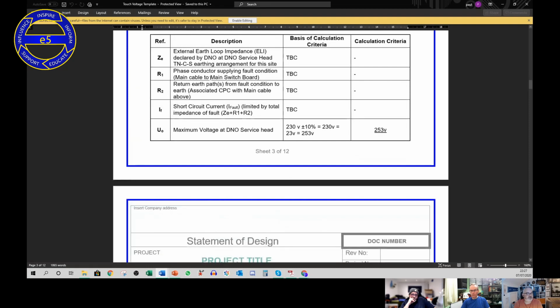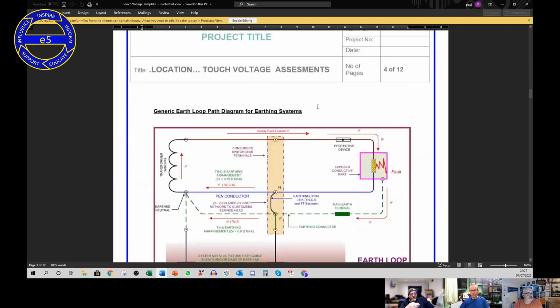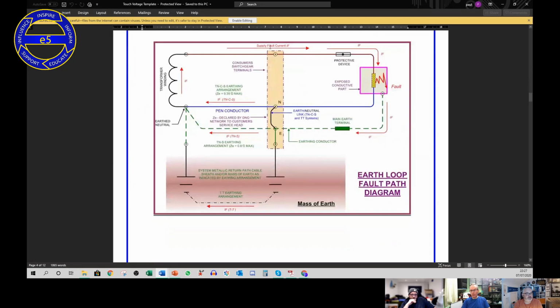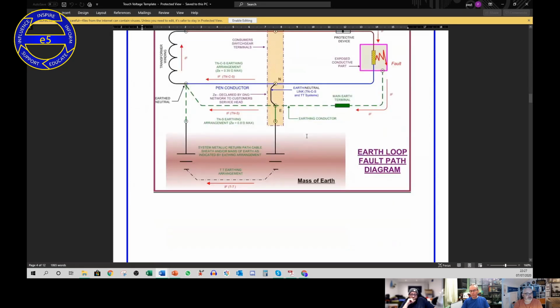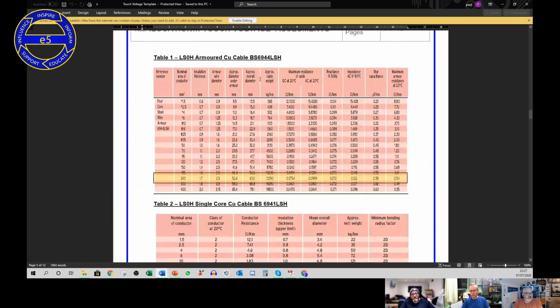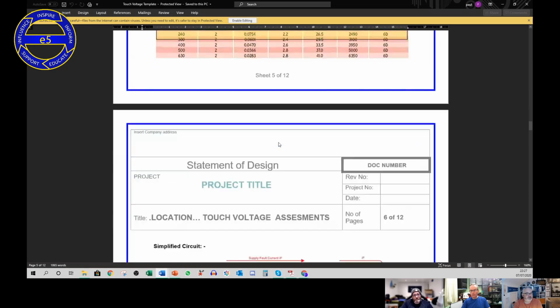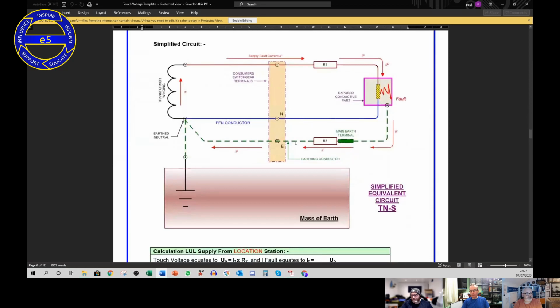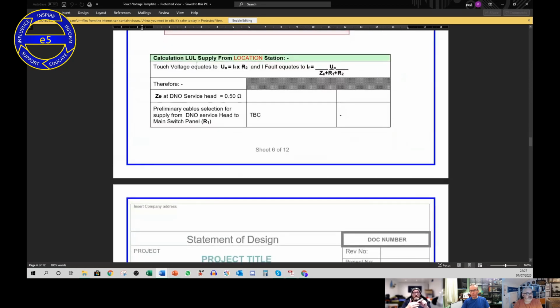This is for a London Underground job, and we basically said, look, ZE, R1, R2, IF. What the basis was, we went and got eventually the formulas. We looked at creating diagrams that showed the earth fault loop. We then got the LSOH armored cable details so that we could plug this all in. We did a simplified circuit on TNS, and we had touch voltage equates to UO equals IF times R2, and fault current equates to IF equals UO over ZE plus R1 plus R2.